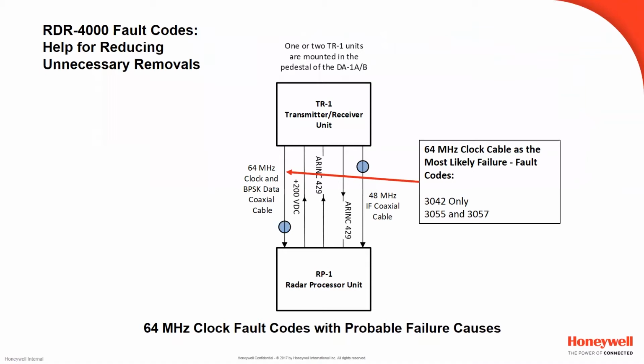In our next section, we're going to concentrate on the 64 megahertz clock cable. We've already mentioned that it's a synchronizing clock for the RP1 and also for data communications using the BPSK data. But now is a good time to mention troubleshooting of both the 64 megahertz and the 48 megahertz cable, if per the fault codes there's a suspicion about a problem with one or both cables. Of course, with coaxial cables, even though these are VHF frequencies and not microwave, you really can't troubleshoot them visually that well, or by resistance checks using an ohm meter.